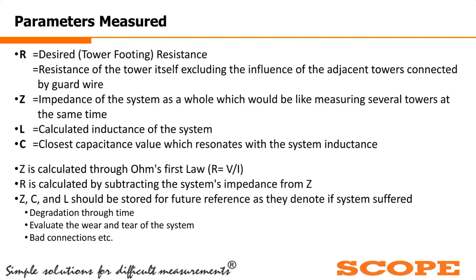These Z, L, C values are stored and these four values are monitored and referred to for future reference, to measure the degradation of the tower footing over time, evaluate the wear and tear of the system, and see if there are any bad conditions. So to analyze this type of data, we require these four parameters measured by the tower footing resistance meter.